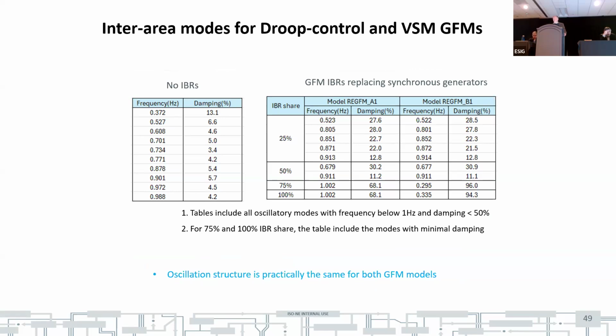Okay, this slide shows what would be the difference between modeling of grid forming inverter if it's a virtual oscillator or just droop-based control. And the table on the right side shows that practically it doesn't matter, because the structure of oscillation remains the same and the property is the same. The more inverters you have, the better the dynamic properties of the system are.